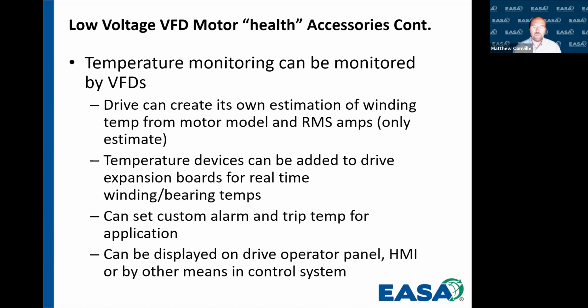So instead of waiting until a failure may occur, we can use this for predictive purposes to see when something has changed. And that can actually help prevent bearing failures as well. The same can be said for windings. You might also add an ambient RTD, and this ambient RTD can be used in instances where we have wide ambient temperature swings, where it could go anywhere from 32 to 115 degrees Fahrenheit, or 0 to, let's say, 40-ish C over the course of a day. And you can just look at that change in temperature versus an absolute. And we can display all these things on the drive operator panel, again on the HMI, or even on somebody's computer if the industrial network is connected to somebody's computer or phone.